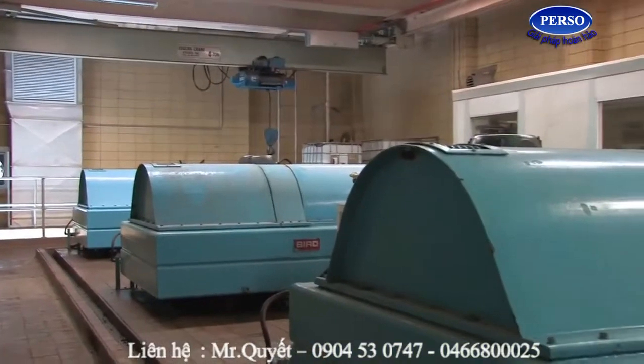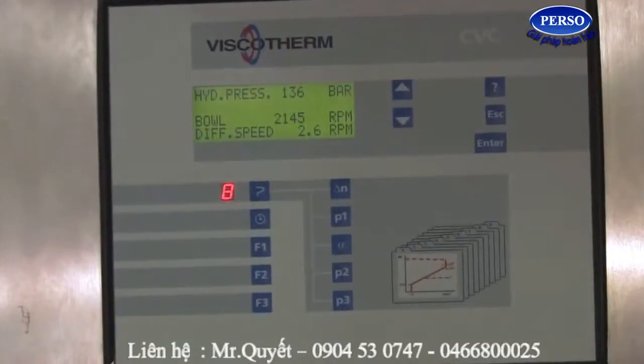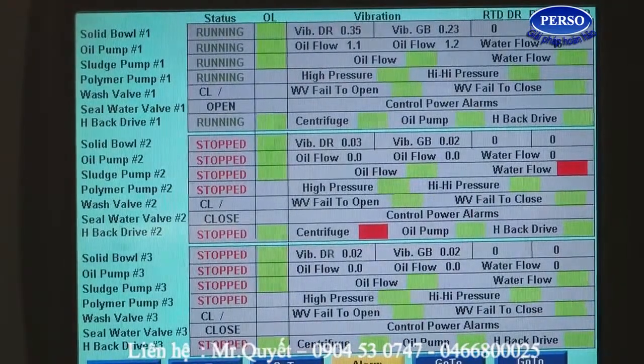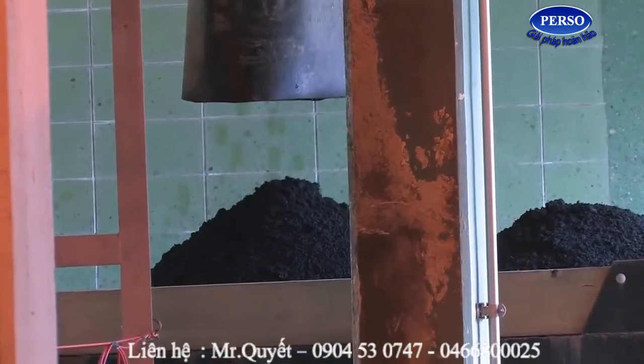We're in the dewatering control room, and here we're taking the solids that were wasted out of the system. And how we do that is we have 3 centrifuges, and this room is manned about 50% of the time in order to monitor that process. Over here we have the controls. We monitor the speed that the centrifuges are spinning, the polymer dose, and the polymer is a binding agent to bring those solids together. As the centrifuge throws those solids out, you need something to help develop what we call a cake. And that cake is then disposed of at the landfill.